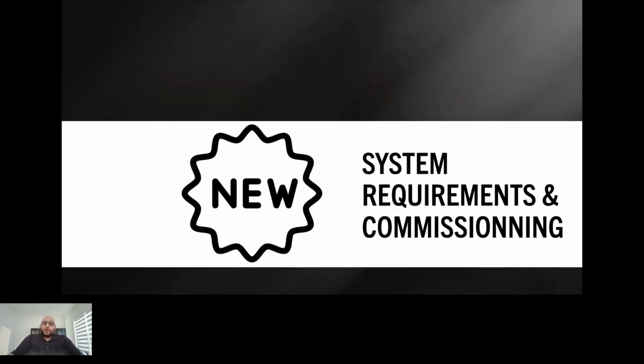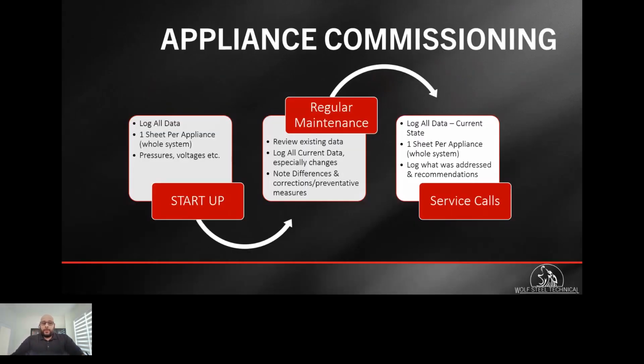So for the system requirements and commissioning, let's discuss what's required from a replacement standpoint. We don't want to forget to log all the data on service/commissioning sheets, so you have not only a baseline performance and comparison, but also a record of any work you have done in the event you need it for whatever reason. This will include how much refrigerant was charged in the system, static pressures, settings, and your delta T's.